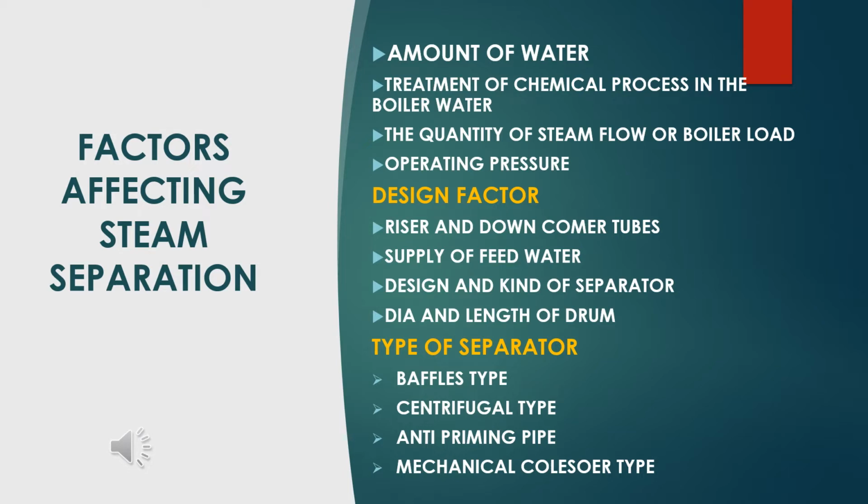The quality of feed water is very important to the boiler. The feed water should be in the range of the vendor design. It should not have greater TDS, and it should be in a specific range of pH. It also involves which type of process you are using to purify your water. Which method you use doesn't matter, but the quality of water fed to the boiler should be pure, otherwise it will badly affect the purity of steam, and the carryover will increase.